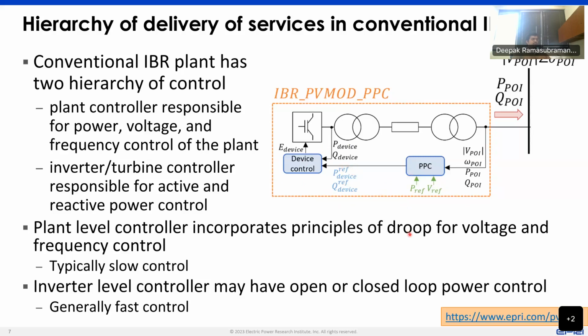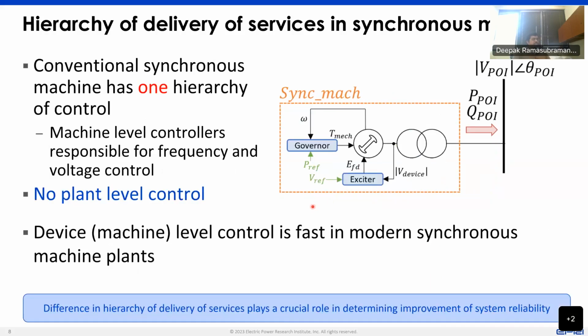So the plant level control has principles of droop incorporated into it for voltage and frequency control. And this is typically a slower control over multiple seconds. And the inverter control can be either open loop or closed loop, and is usually a very fast control that can have power control enabled on it. Now, if we compare this conventional IBR plant with a synchronous machine, a synchronous machine has only one hierarchy of control. Every controller of the synchronous machine is at the machine level or at the device level. There isn't usually a plant controller.